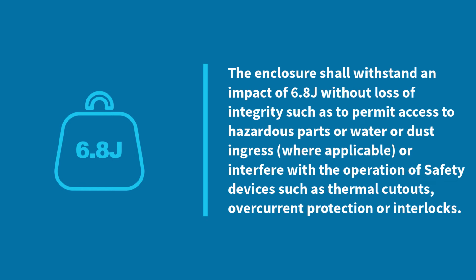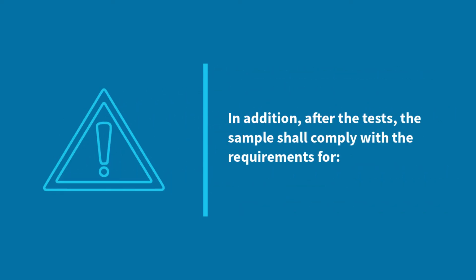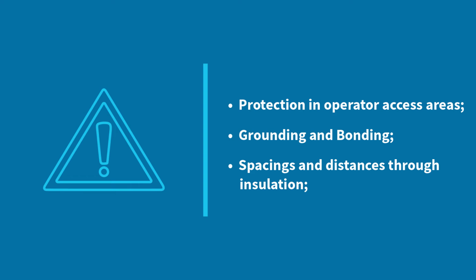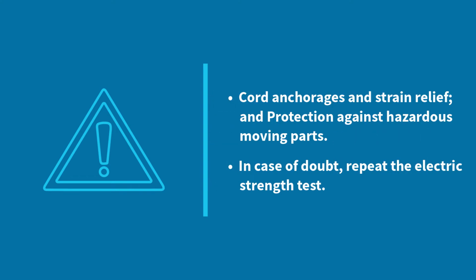Acceptance criteria. The enclosure shall withstand an impact of 6.8 joules without loss of integrity such as to permit access to hazardous parts or water or dust ingress, where applicable, or interfere with the operation of safety devices such as thermal cutouts, overcurrent protection, or interlocks. In addition, after the tests, the sample shall comply with the requirements for protection in operator access areas, grounding and bonding, spacings and distances through insulation, cord anchorages and strain relief, and protection against hazardous moving parts. In case of doubt, repeat the electric strength test.